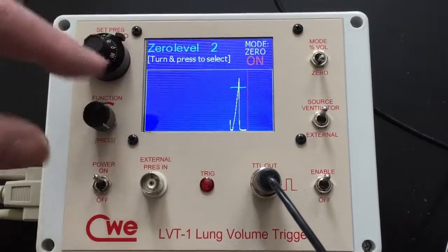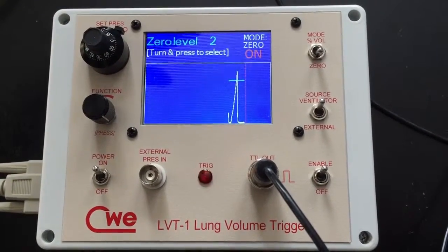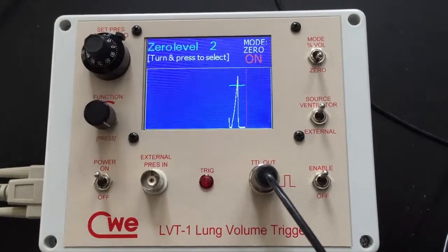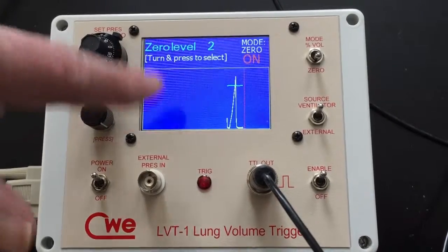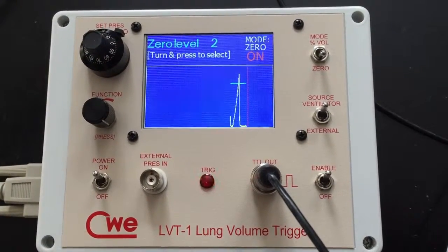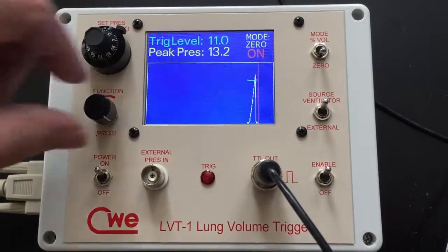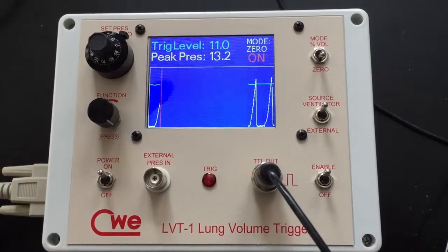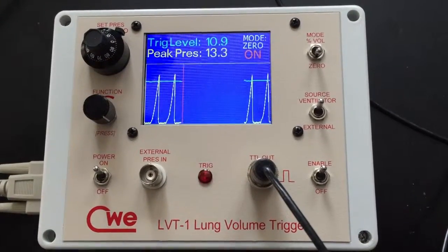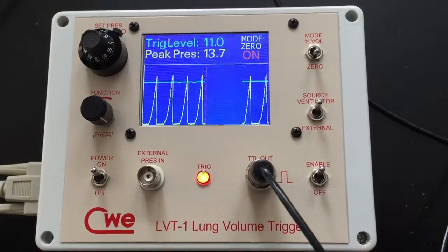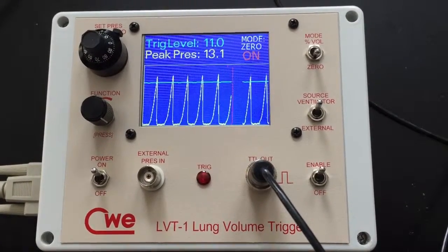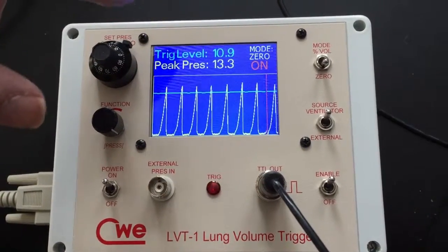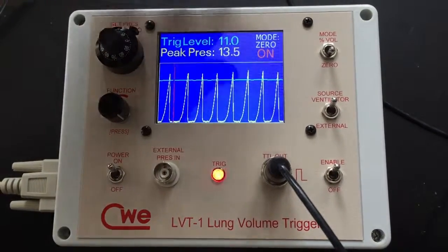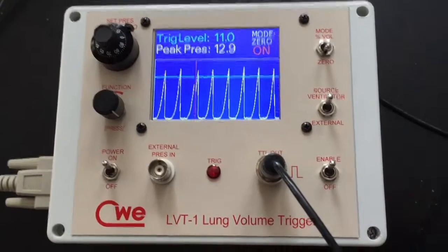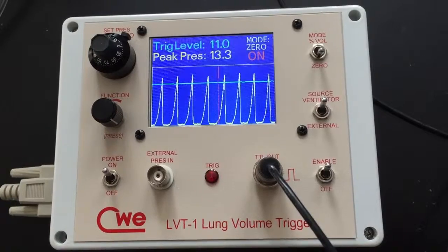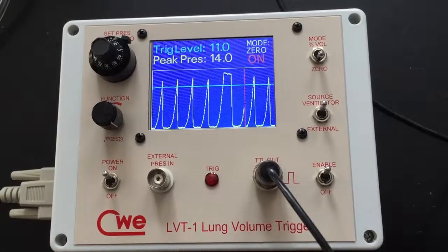It's in centimeters of water, and it just sets a threshold of pressure that the instrument looks for to detect zero. So if you had a really noisy signal, or you had a little bit of zero offset, you can change that, and all of these functions will time out. So if you accidentally hit something, it'll just recover itself in about 10 or 15 seconds. And in the background, even while you're doing these functions, the background triggering is always going on. So that doesn't stop, that's running in the background. And those are basically the current functions of this.